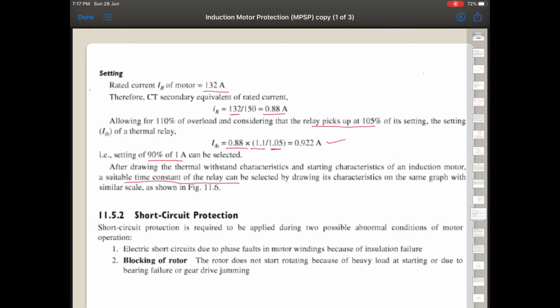And another is blocking of the rotor. So the rotor does not start rotating because of heavy loads. This is one reason, and it may also be due to bearing failure or gear drive jamming. So any of these three reasons may cause blocking of the rotor.